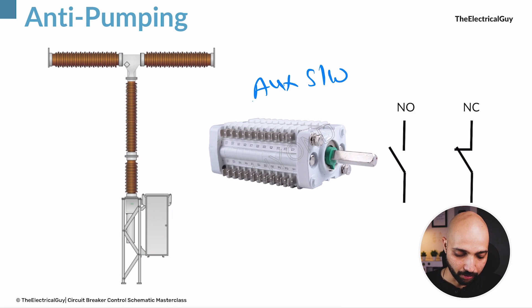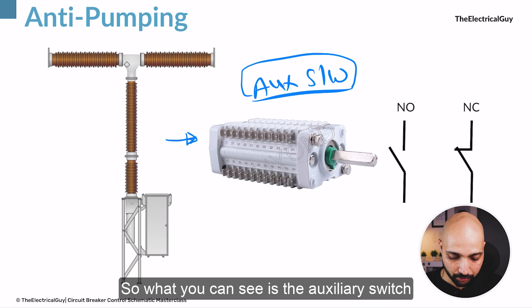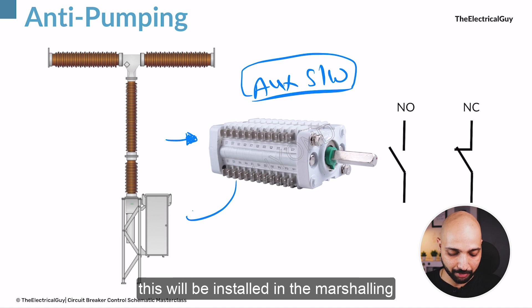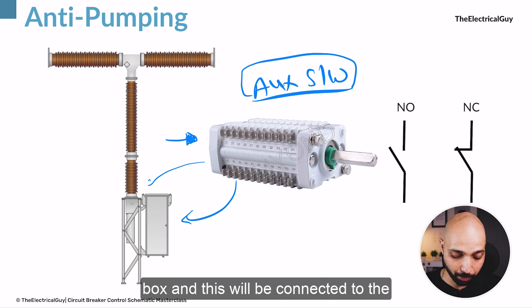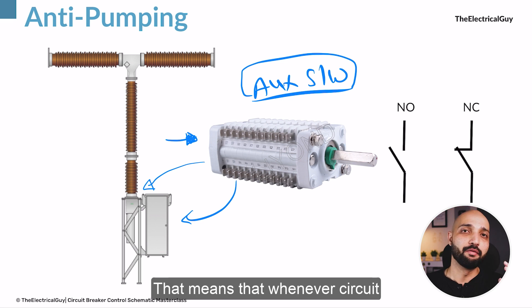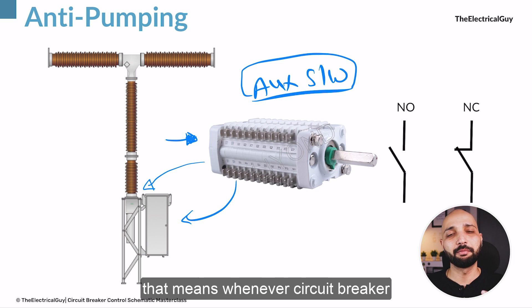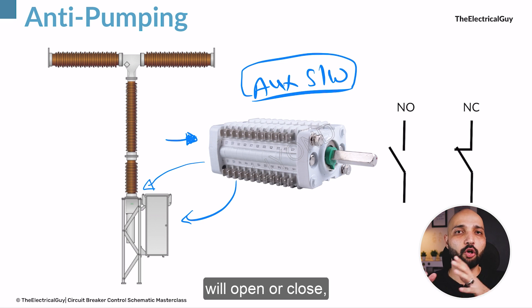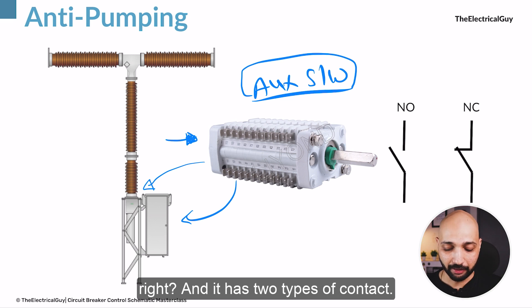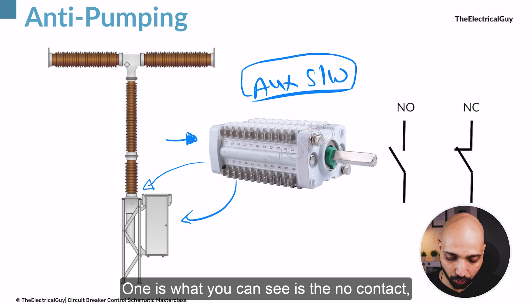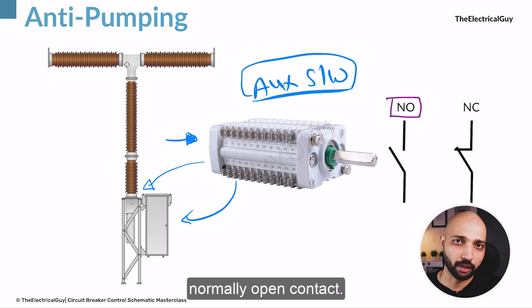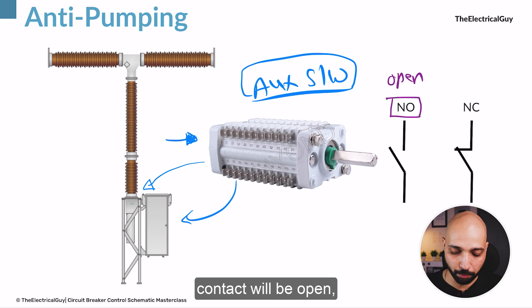The next equipment is the auxiliary switch of the circuit breaker. This auxiliary switch will be installed in the marshaling box and will be connected to the operating rod of the circuit breaker. That means whenever the circuit breaker operates — whenever it opens or closes — this switch will also operate with it. It has two types of contacts: the NO contact, which is the normally open contact whose default position is open.